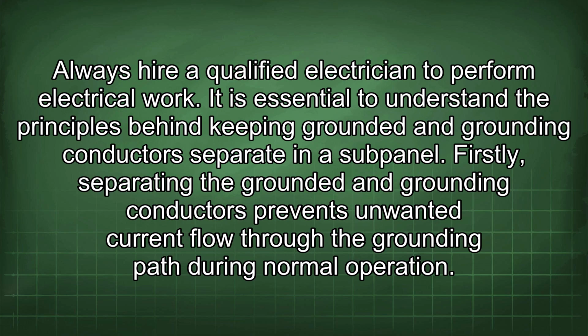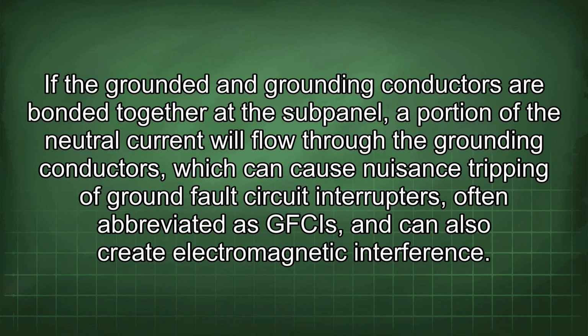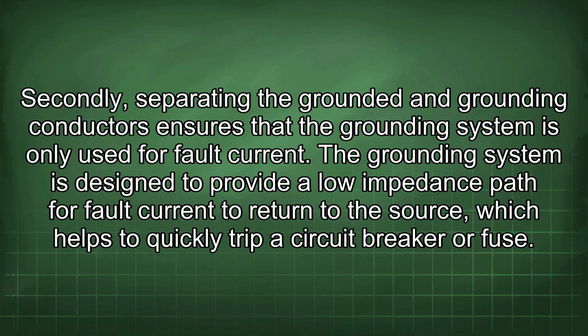It is essential to understand the principles behind keeping grounded and grounding conductors separate in a subpanel. Firstly, separating the grounded and grounding conductors prevents unwanted current flow through the grounding path during normal operation. If the grounded and grounding conductors are bonded together at the subpanel, a portion of the neutral current will flow through the grounding conductors, which can cause nuisance tripping of ground fault circuit interrupters, often abbreviated as GFCIs, and can also create electromagnetic interference.